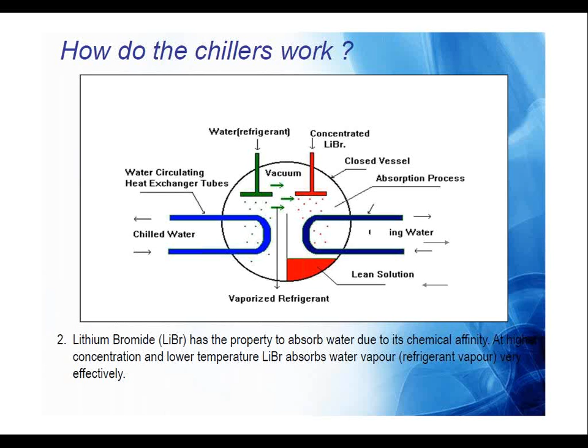Now this lean solution or the dilute solution, with the help of the absorbent pump, we are pumping it to the high pressure and high temperature generator. In the generator, we are actually using live steam or hot water, any heat source that is getting used in the generator only. So based on the heat source, we term this machine as steam fired vapor absorption machine, exhaust fired vapor absorption machine, hot water fired vapor absorption machine, or direct fired vapor absorption machine. So this terminology is based on the type of heat which is getting utilized in this generator.